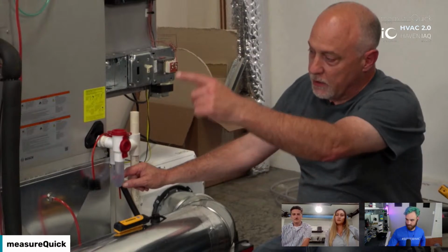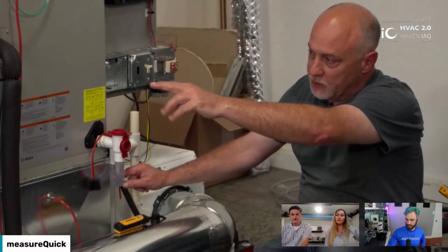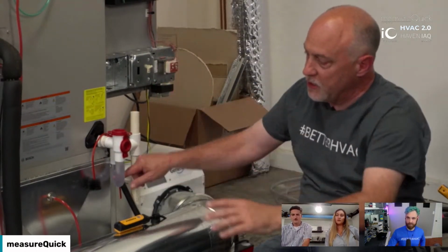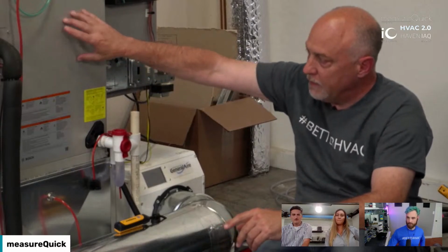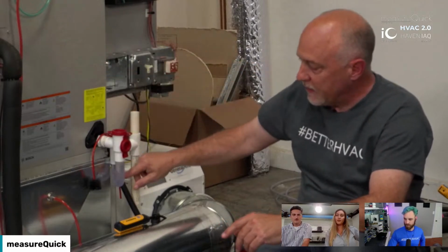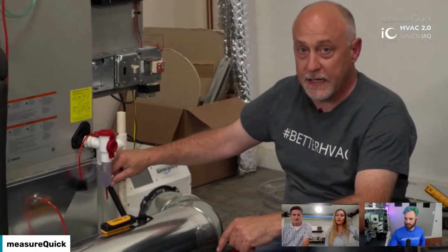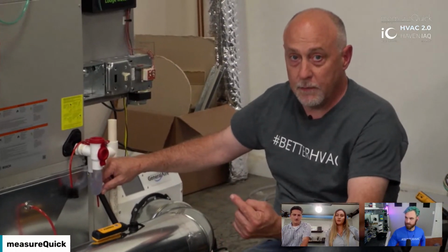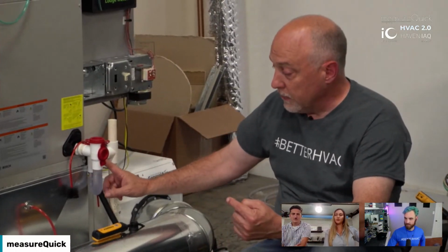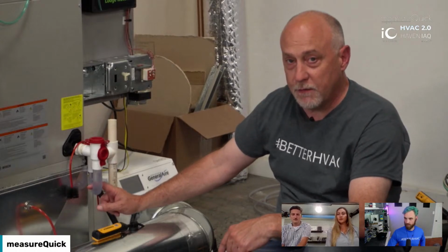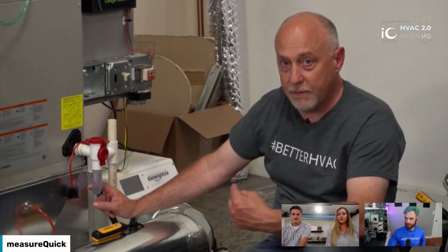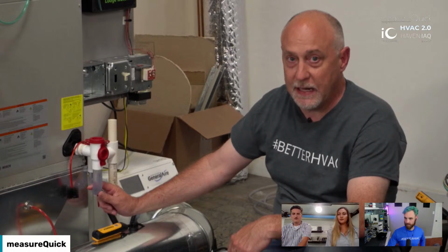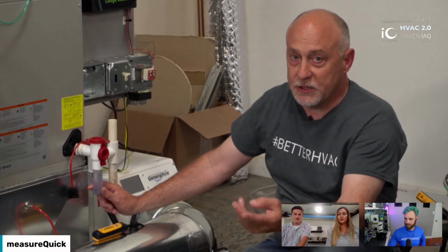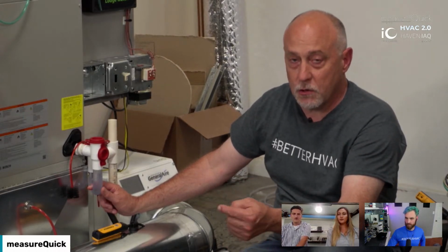When dirt comes down, bypassing your filters or not getting good filtration, it ends up on this coil. The water rinses off the coil and down the drain, and that's a good indicator that we're getting dirt in places we don't want it. So the clear trap is a visual indicator for us that we have clean condensate, because condensate is distilled water - if you've ever bought distilled water at the store, there's no dirt in it.